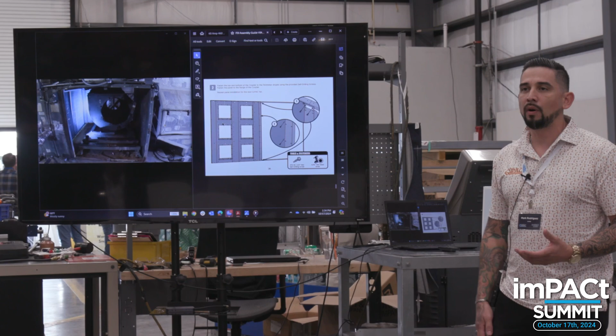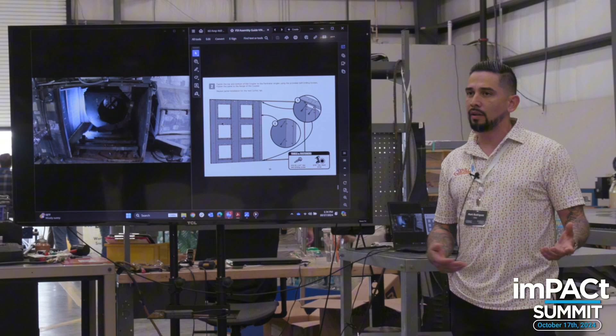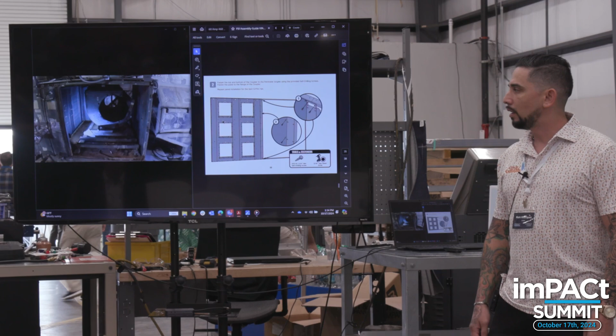So ripping out the old stuff, the shaft, the housing, the inertia base, or what have you, depending on the size of the unit. But once you get all that out and cleaned up, putting in the Q-PAC is pretty simple, as long as you've got a nice firm perimeter to put the angle on, making sure it's not rusted or corroded, because you want a good solid attachment to the unit itself.